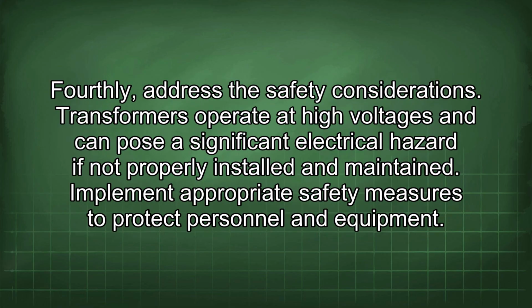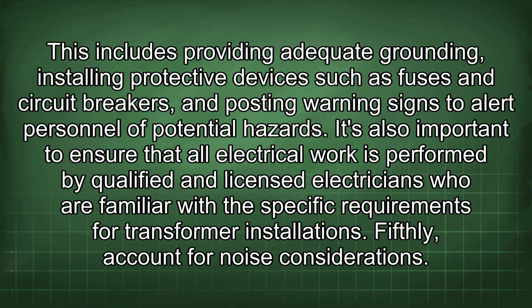Fourthly, address the safety considerations. Transformers operate at high voltages and can pose a significant electrical hazard if not properly installed and maintained. Implement appropriate safety measures to protect personnel and equipment. This includes providing adequate grounding, installing protective devices such as fuses and circuit breakers, and posting warning signs to alert personnel of potential hazards. It's also important to ensure that all electrical work is performed by qualified and licensed electricians who are familiar with the specific requirements for transformer installations.